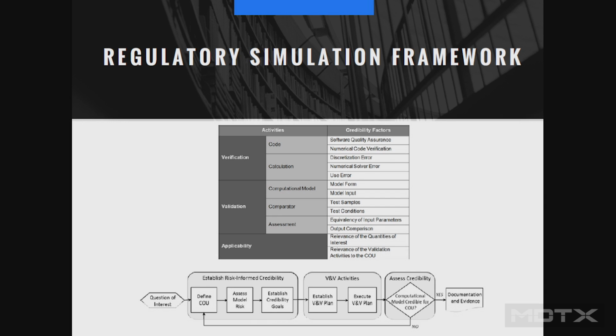And what those documents do is they provide this type of framework that you can use in order to include that simulation data as part of your FDA submission. They want to make sure that you're hitting all of these areas when you bring them data that you want to make design decisions off of. They want to make sure that you're covering things like code verification, that you've looked at all the different sources of error, that you've made sure your context of use is appropriate for this type of model, and that you check all of those boxes. So they go through in those two documents and give you that framework through this type of flow chart and these types of design frameworks to get you through that process, so that you can provide all that to them and get information out.